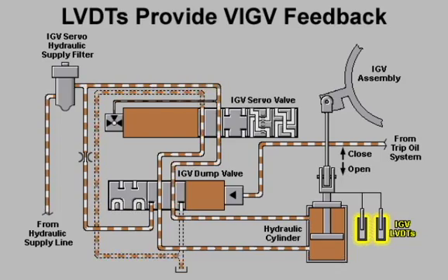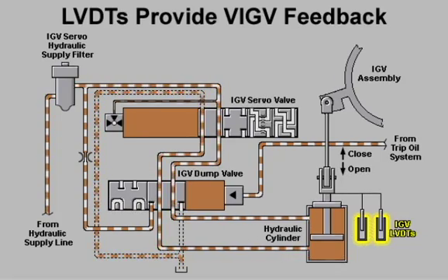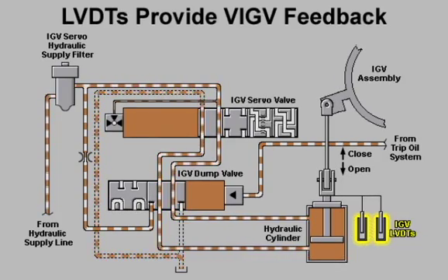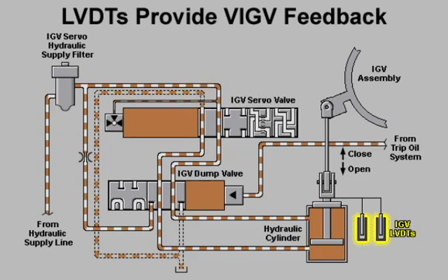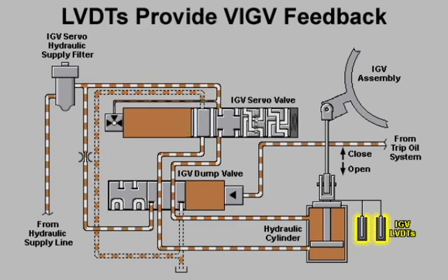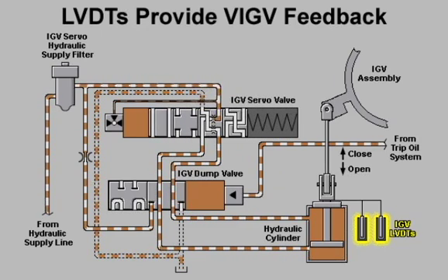The core of each LVDT moves as the angular position of the variable inlet guide vanes changes. This provides feedback to the control system concerning the actual VIGV angle.